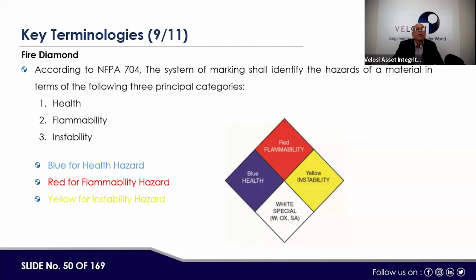That is zone 2. Now, the other part, from a terminology point of view, is the NFPA 704 diamond concept. The diamond is a system used in the MSDS, material safety data sheet, of any fluid. In that MSDS, these questions are normally answered: first the flammability, then health impact, then reactivity. Yellow is reactivity. Here we are saying health, flammability, instability, and instability is sometimes also called reactivity. Blue is for health hazard, red for safety or flammability, and yellow is for reactivity. So in the MSDS, all materials are categorized as per this diamond, and accordingly their handling procedures are managed and developed.